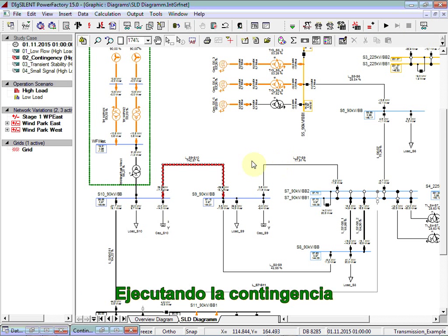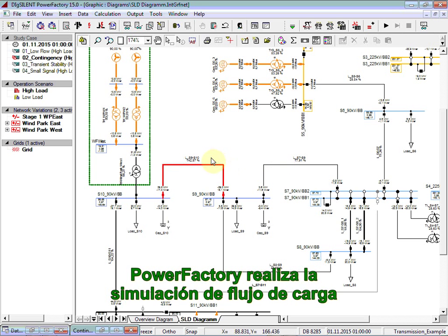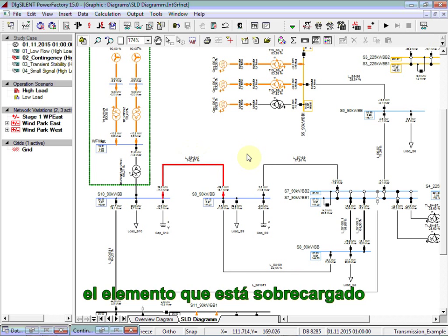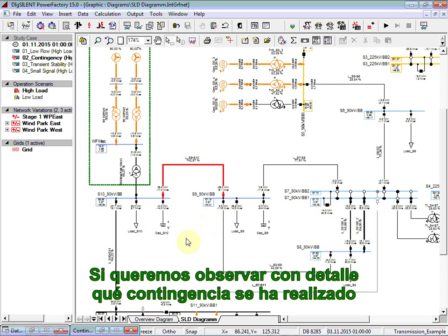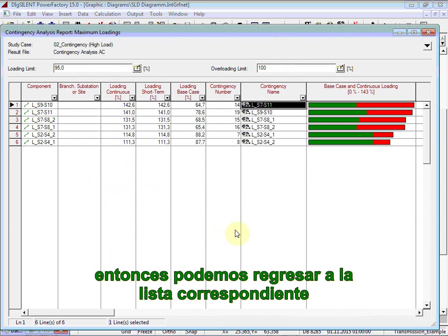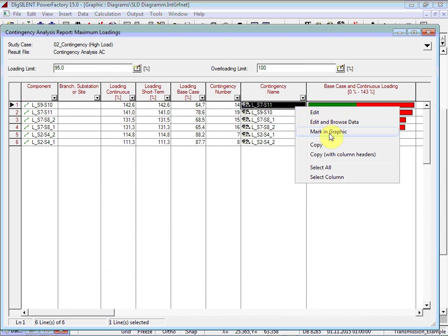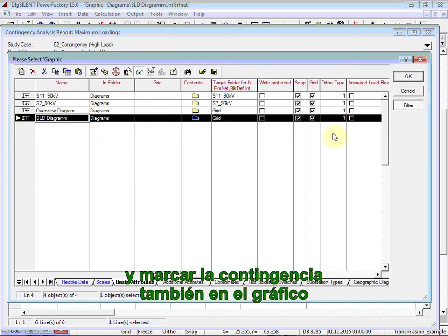By executing the contingency, PowerFactory runs the load flow simulation. Here we notice, as expected, the corresponding element being overloaded. If we want to take a look at which contingency was performed, we can return to the corresponding list and mark the contingency also in the graphic.